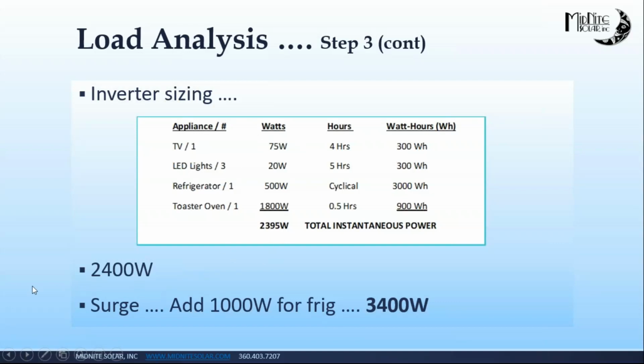Then there's surge capacity, which we'll also cover in inverter sizing. Even though this says 2,400 watts, I'm going to add a surge for the refrigerator, because when that compressor fires up it draws a lot of current. That's called a surge, so my inverter needs to support a minimum of 3,400 watts instantaneously. I'd probably go with a 4,000 watt inverter as a buffer. There are also reactive power elements with AC that we won't get into, but I'd upsize it.